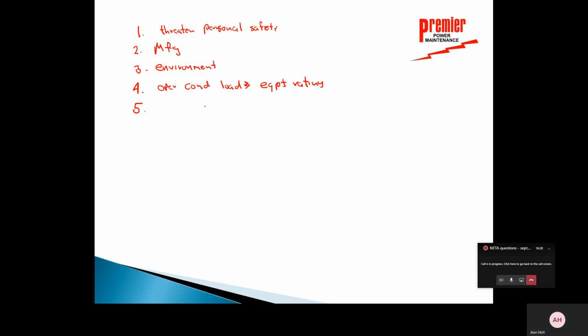Number 5, expensive equipment repairs. You might want to take that into account, and that's what's listed in NFPA 70B. If it's going to cost a ton to repair this equipment, maybe I ought to check it out before I have to pay for that repair. Number 6, extensive downtime. If I have a piece of equipment that's not replaceable, it's on a 64-week lead time or something like that, then I need to take care of that piece of equipment because that could be really disastrous to the business. It could be the lost production as part of it too. That's part of the extensive downtime.